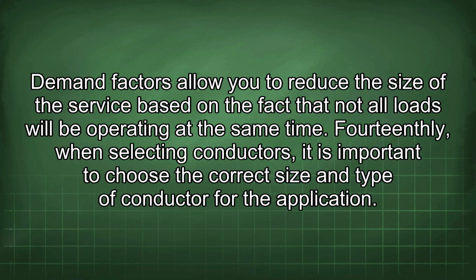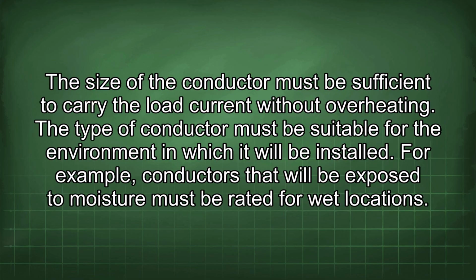14thly, when selecting conductors, it is important to choose the correct size and type of conductor for the application. The size of the conductor must be sufficient to carry the load current without overheating. The type of conductor must be suitable for the environment in which it will be installed. For example, conductors that will be exposed to moisture must be rated for wet locations.